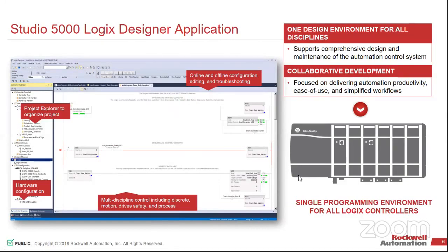But for the big things you'll see, as of version 24 we introduced the Logical Organizer. That gives us the ability to do a lot of library modifications inside of the Studio 5000 world, where we can copy and paste pieces of code and any dependencies, the UDTs and AOIs that existed. A big example we used to use: if you have a boiler 1 and you want to make a boiler 2, all you have to do is copy it over, and all the tags that existed for it get moved over. That was introduced in version 24.